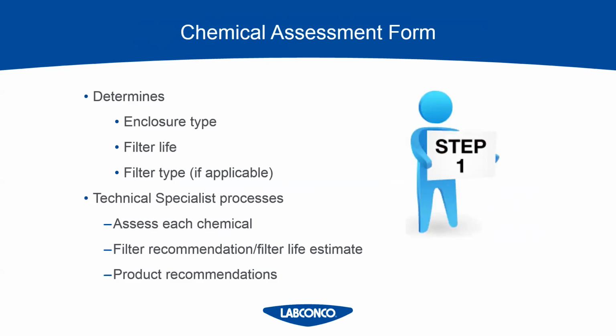So this is always step one, and basically this has to be done regardless of manufacturer. If you go to any manufacturer with ductless hoods, they will make you fill out a chemical assessment form. If you are interested in a ductless hood, you have to be prepared to give very detailed information on the application. And if you come back to me and say, well, it's going to change every day, we're going to tell you it's not going to be good for a ductless hood.